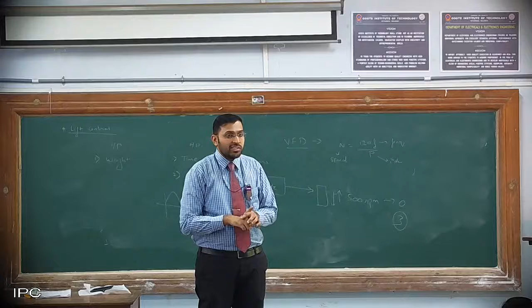What do I have to do? I have to increase the frequency from 50 Hertz to 60 Hertz. Because N is directly proportional to frequency. If frequency increases, speed increases. Frequency decreases, speed decreases. There is a complete algorithm, and what we are talking about in electrical is only the equation. 99% is complete software and electronics inside. Fine. So at 60 Hertz, what has happened? Again 500 RPM.